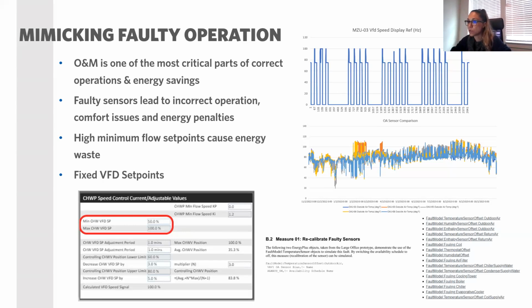But as I mentioned, there are ways to capture this incorrect operation in an energy model, especially with EnergyPlus. You can also mimic faulty sensors. These are some examples: outside air dry bulb, wet bulb, chilled water outlet temperature. So you can actually create a digital replica of that faulty operation.